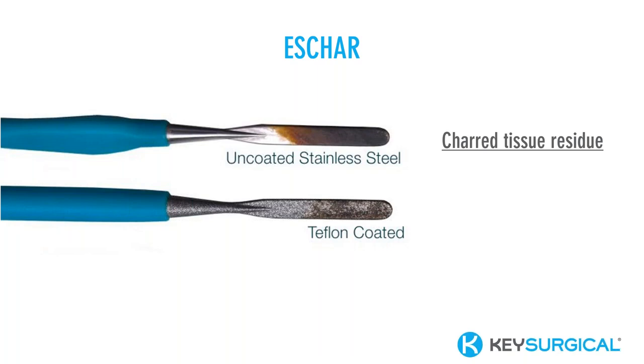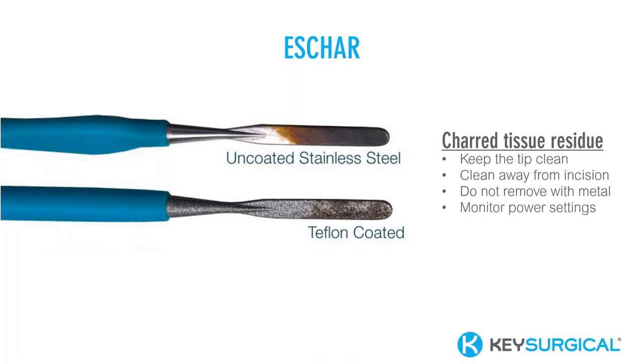So let's talk about some best practices for caring for these instruments during the procedure. First of all, keep the tip clean at all times during the surgical procedure and wipe it between uses, just like you wipe the counter as you're cooking. You don't wait till the end, especially with caramel. Holy moly, that would be so challenging. Clean the tip away from the incision, not just wiping it right into the field. Do not clean the active electrode tip with metal. That can cause insulation damage and other damage to that instrument. Monitor the power settings. This one isn't as clear, but a lot of times buildup on these instrument tips can actually lead to an increased need for power, and that can increase the likelihood of other complications.